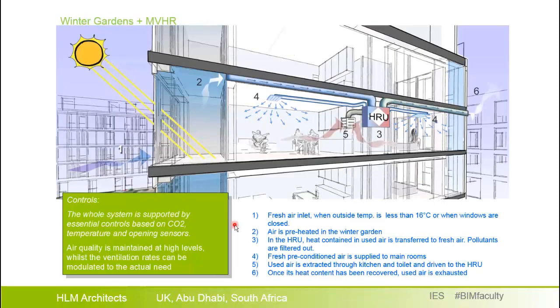Here is a scheme of the simple integration of the two systems. On the left hand side, fresh air is taken into the winter garden, preheated, and then led directly to the heat recovery unit where heat is recovered from used air, and then fresh air is supplied to the rooms. To simulate this, we use two modules in IES: MacroFlo and Apache HVAC.